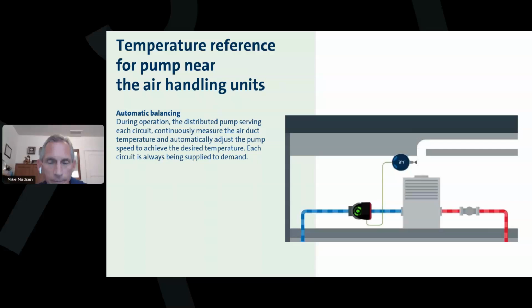Okay. So here's one. How are the pumps ramping up and down? Do they have little variable frequency drives in there? They do. So you'll probably remember the smart pumps, the little Magna 3 circulators. Those all have integrated VFDs, and most manufacturers have a pressure sensor or temperature sensor in those little circulators. And then you'll remember the IE5 motors that I showed at the beginning of the presentation. Those have an integrated VFD also.